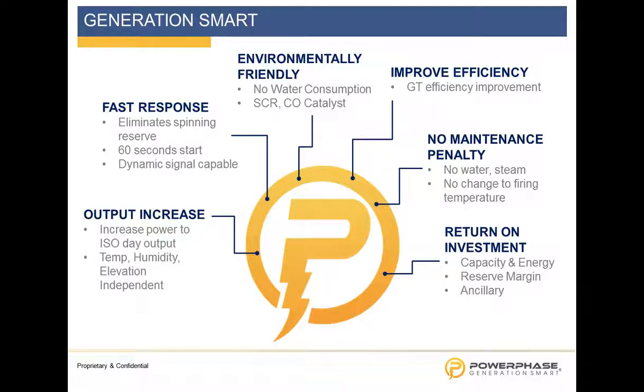So to summarize a few of the points here, it's an output increase, and I think we've had a lot of discussions in the past around how air mass flow increases the output. By adding more mass, the gas turbine adds more fuel, and since we add a constant amount of mass at all ambient temperatures, humidities, and elevations, it doesn't matter if the gas turbine is sitting in Mexico City at 6,000 feet elevation, or is sitting in the Saudi desert at 50 C ambient, or in Indonesia at 100% relative humidity at 28 C.